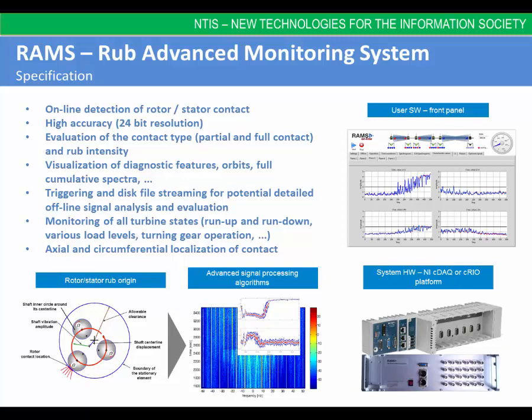The system makes it possible to detect relatively risky or unsafe operating conditions of steam turbines and consequently reveal causes of these conditions. The developed device is globally unique — early and automatic detection and localization of rotor-stator contact, which the system carries out, is unavailable in current machine monitoring systems of steam turbines. The RAMS has up to 32 channels with high 24-bit resolution, which enables evaluation of the contact type and its intensity.